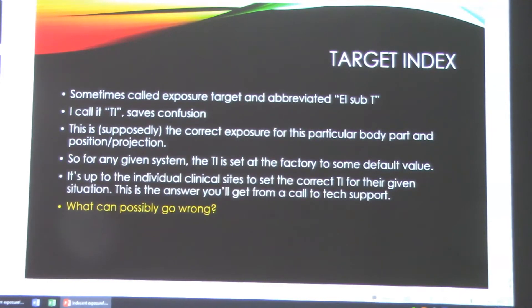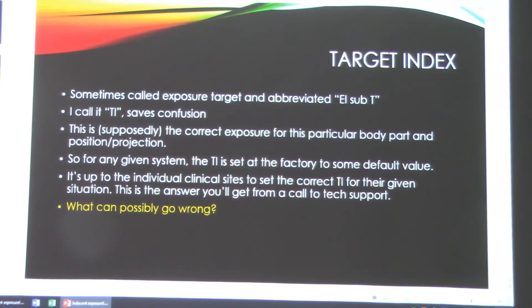Now, target index. Every company that sells x-ray equipment has a target index that they have pre-programmed in for you. The idea is that whenever you get a new piece of equipment, you're supposed to change your target indices to match the techniques that you're using in your department. So basically, it's up to each individual department to set their own target indices. If you call tech support for any image receptor system — Canon, Siemens, Fuji, whatever — they're going to tell you the same thing: you're supposed to be setting your own target indices.